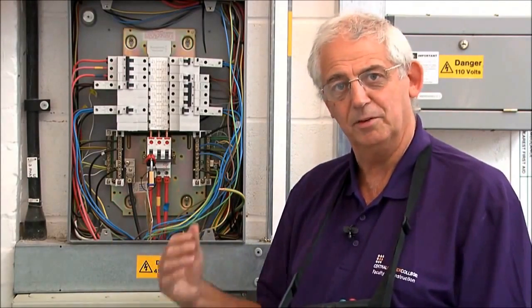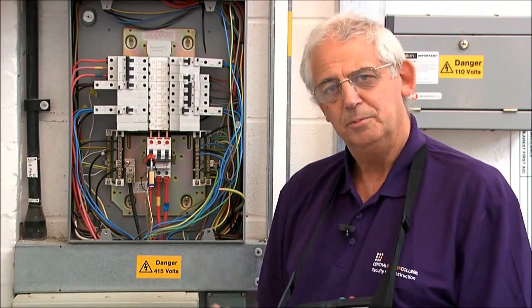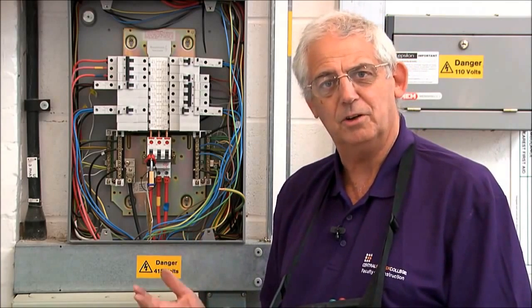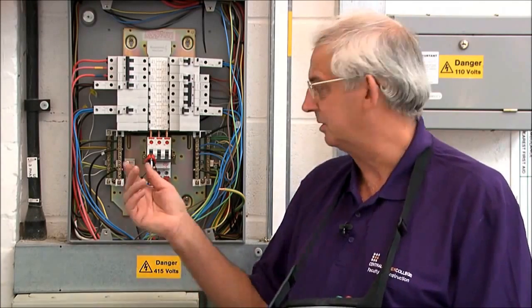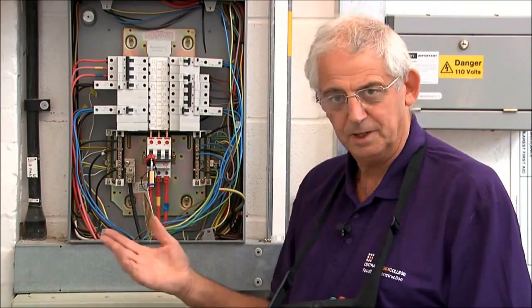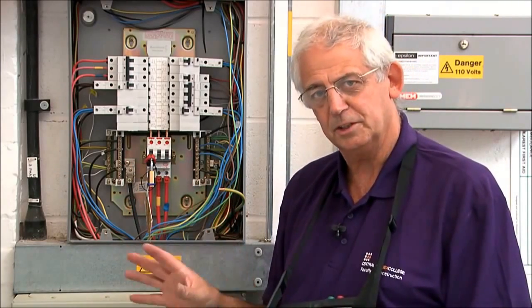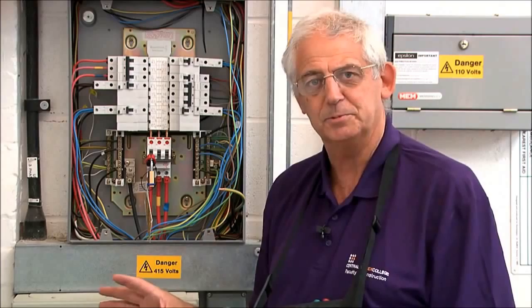We're going to carry out a ZE test. Now obviously to carry out this test I need to take the cover off of the distribution board. Before I do that I must isolate the system. So I've isolated it and locked it off. Everything's safe now. But it's still a live test, so great care must be taken at all times.